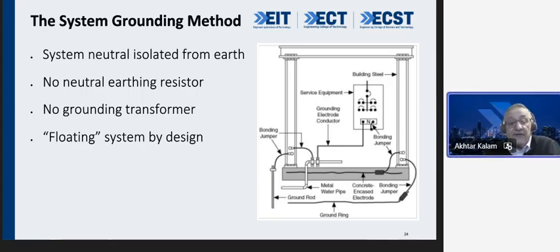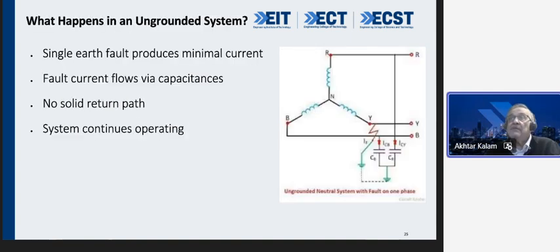Now, if it is an ungrounded system, what is happening? What happens in the ungrounded system? Current is very low, minimal current. My relay did not trip. Fault current is via capacitors. Look at that, it's going to the capacitance. There's no solid return path. The system continues operating, and the fault which is there has not been detected by your protection relay. Very simple. QED, problem solved.